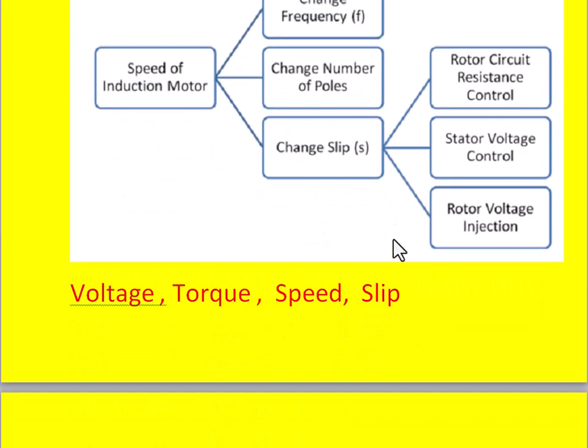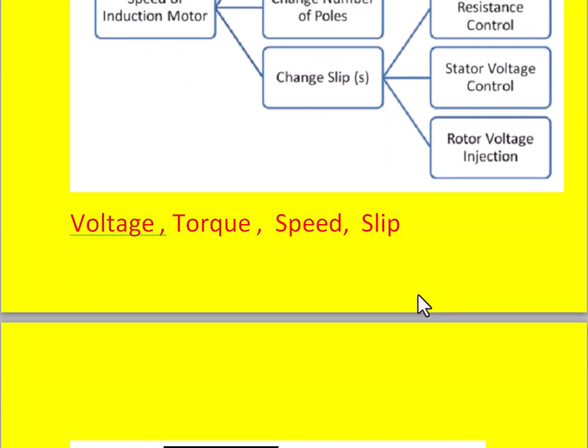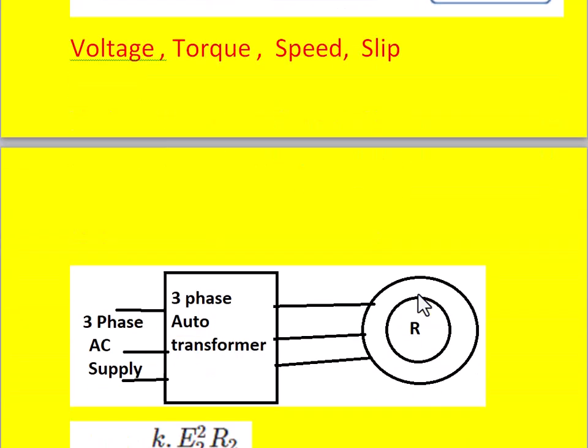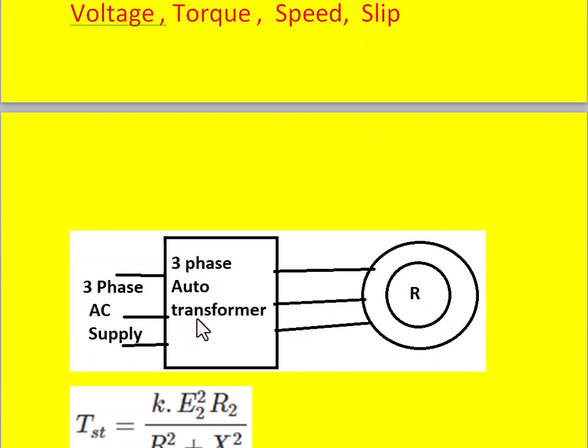In this video, the stator voltage control method will be discussed. In this method, voltage influences the torque, torque influences the speed, and speed influences the slip. The general circuit diagram shows a three-phase AC supply connected to the stator of the three-phase induction motor via a three-phase auto transformer to get variable voltage at the stator terminals.